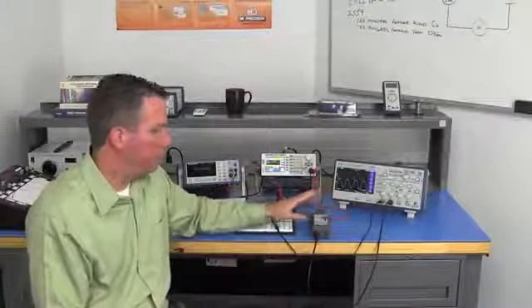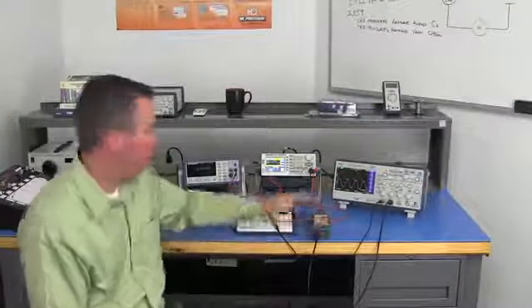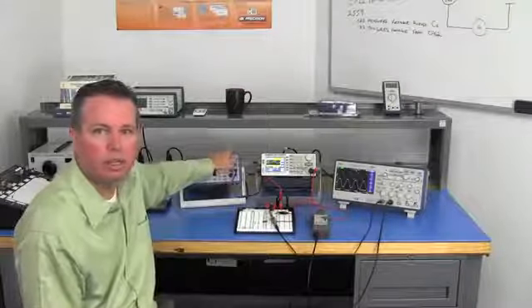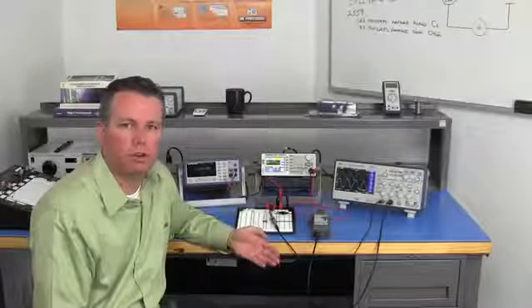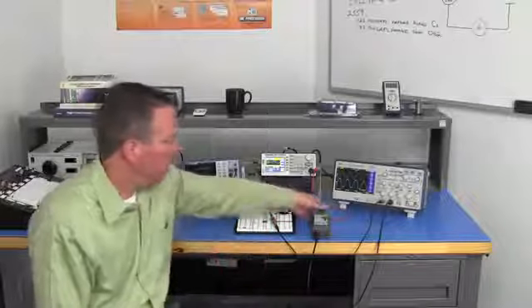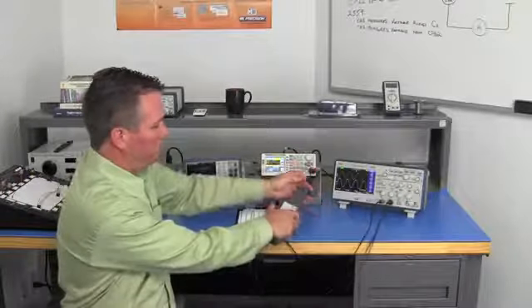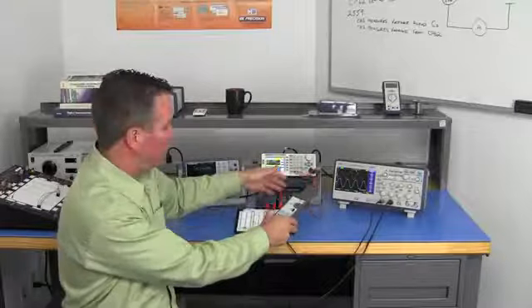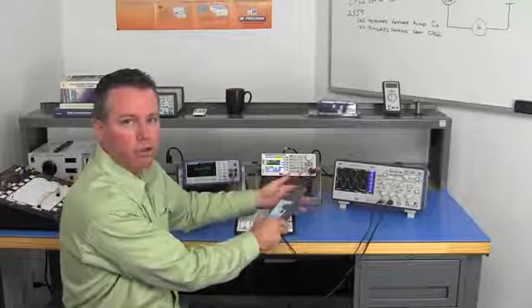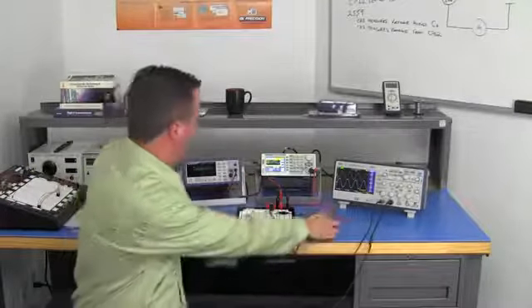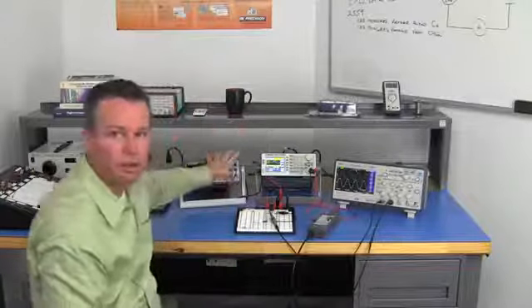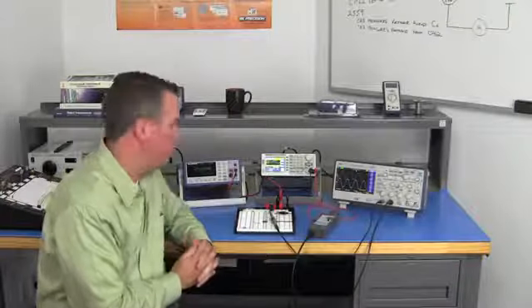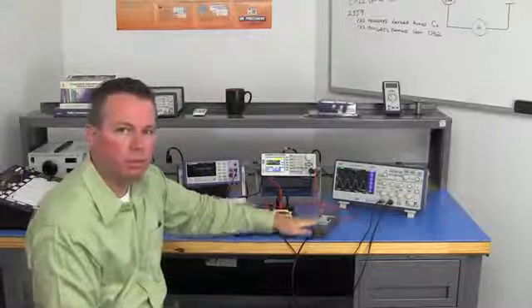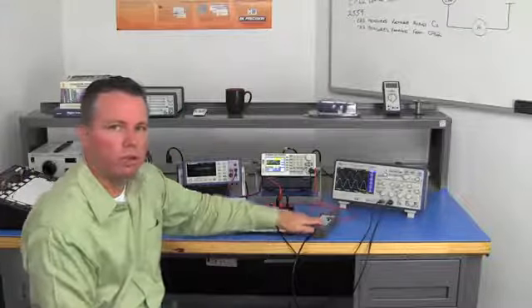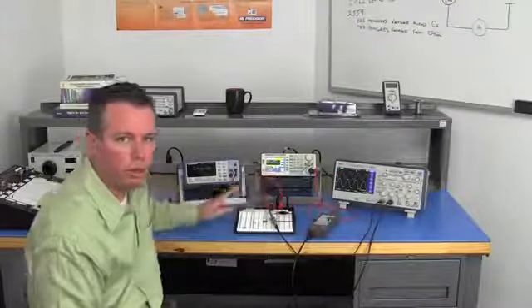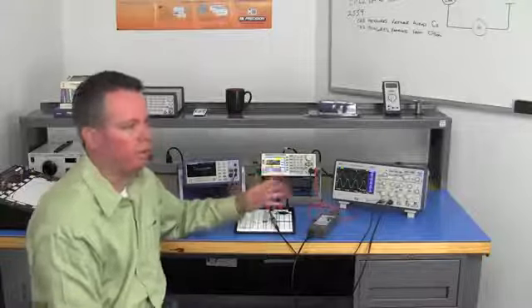A benefit of using a current probe instead of a bench multimeter is that you don't need to break the circuit in order to measure current. You clamp the current probe around one of the supply wires, or any wire that would be in the circuit, and you're able to measure the circuit's current. With a bench multimeter, you need to put it in series and break the circuit to make your measurement. Another benefit of using a probe is that you not only measure the current value like you would with a meter, but you can also see the current waveform.